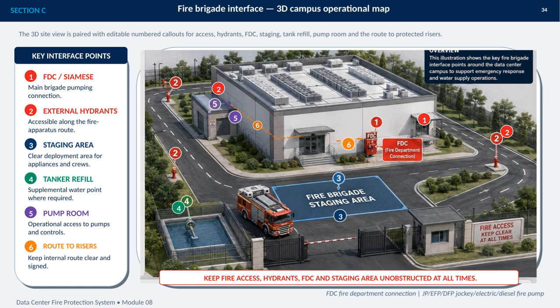The first point is the FDC, or Siamese connection, which provides the main brigade pumping connection. Second are the external hydrants, positioned along the fire apparatus route. Third is the staging area, where appliances and crews need a clear deployment space. Fourth is the tanker refill point, providing supplemental water where required. The fifth point is the pump room, with operational access to the pumps and controls. Finally, the route to the protected risers must remain clear and properly signed, so crews can move efficiently from the external approach to the internal fire protection system.